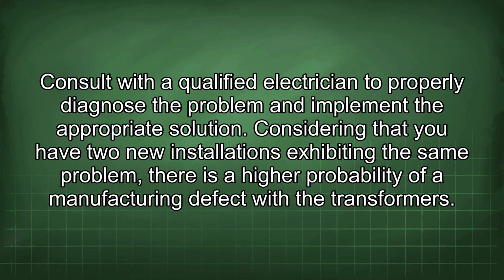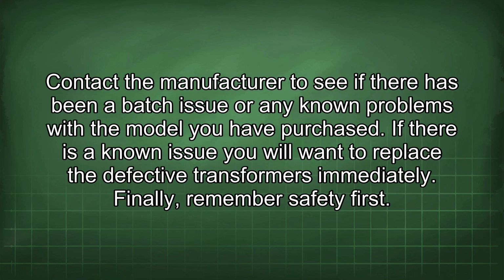Considering that you have two new installations exhibiting the same problem, there is a higher probability of a manufacturing defect with the transformers. Contact the manufacturer to see if there has been a batch issue or any known problems with the model you have purchased. If there is a known issue, you will want to replace the defective transformers immediately.